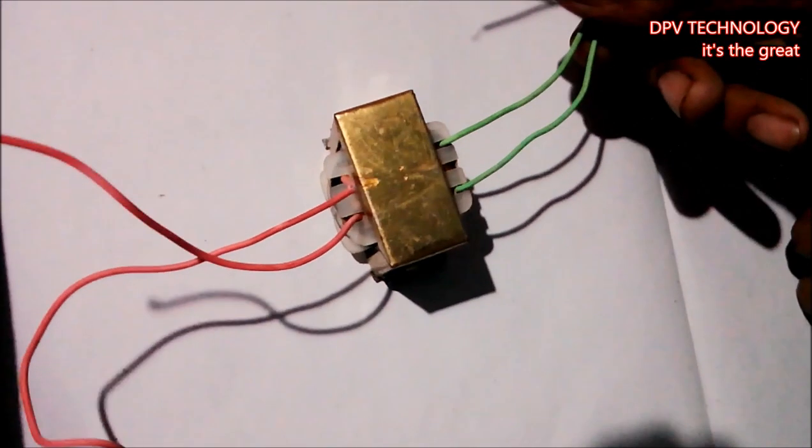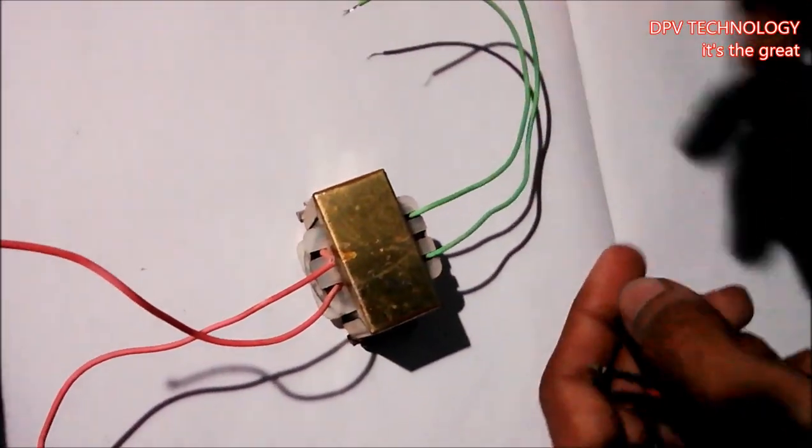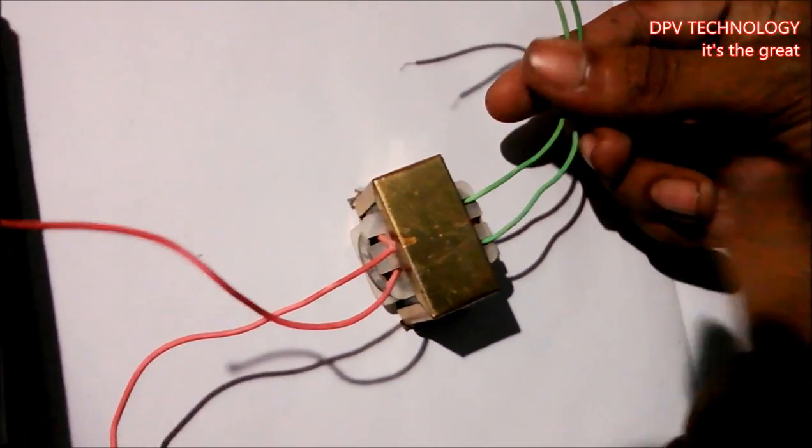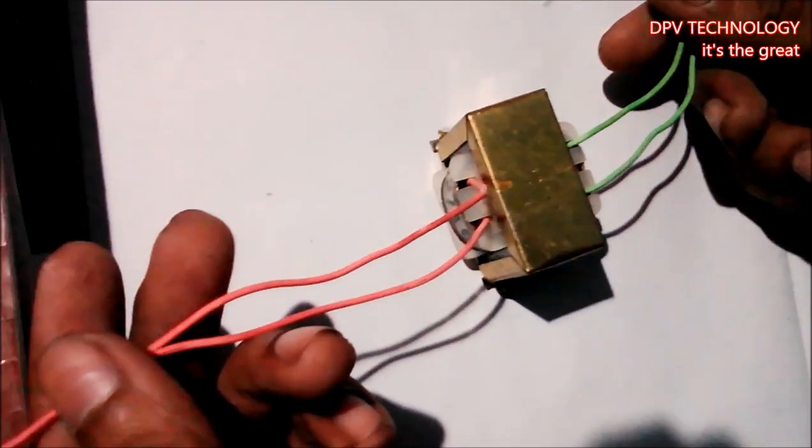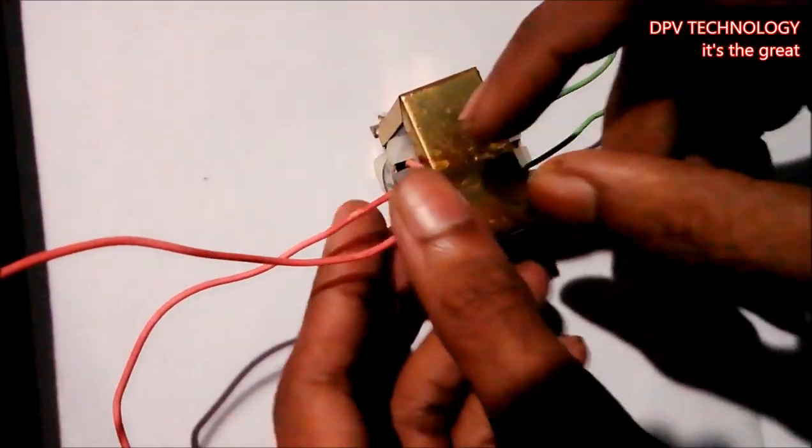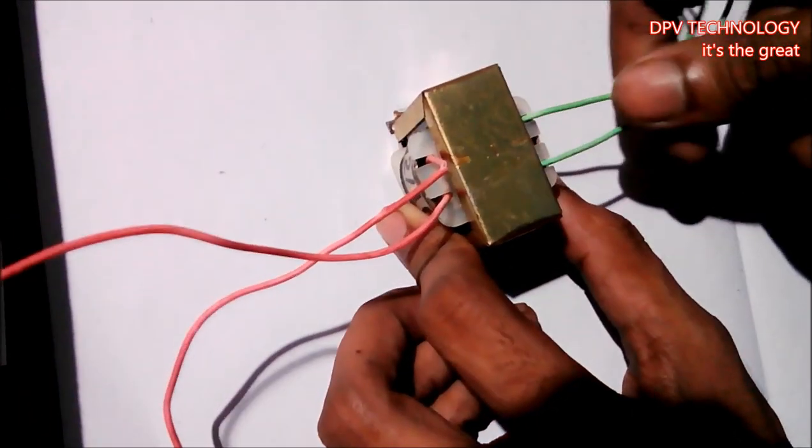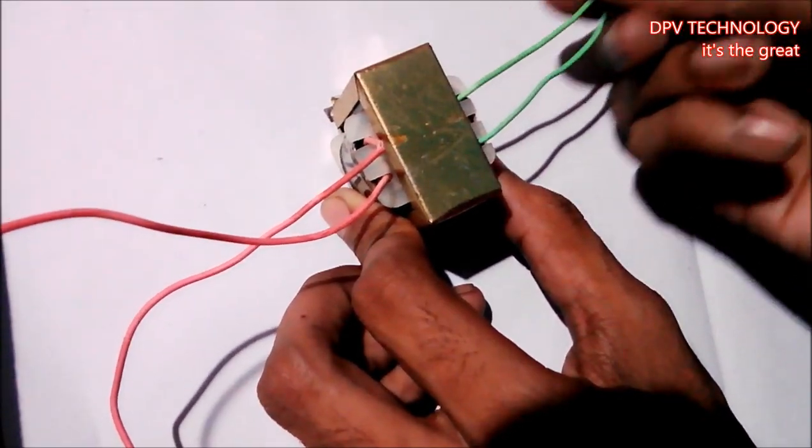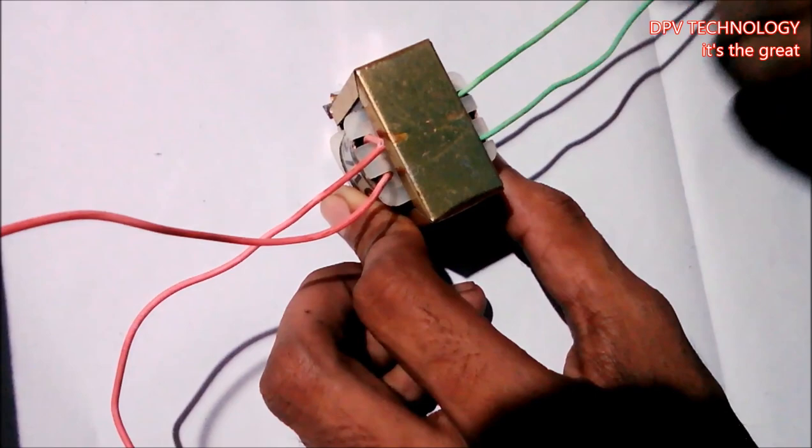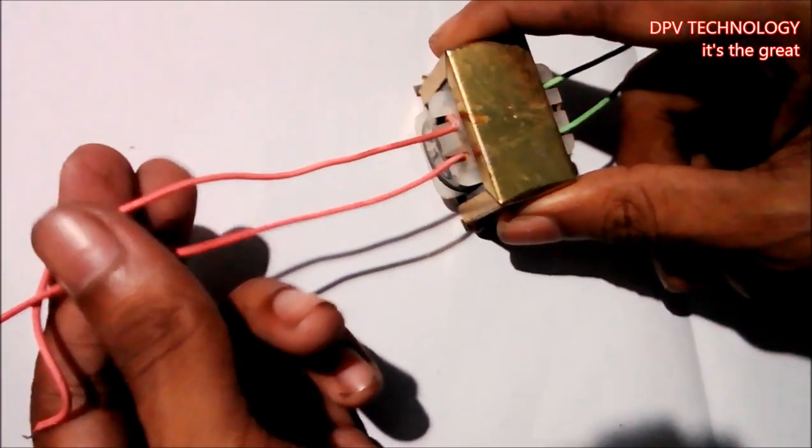Here we have 1.6 kilo-ohms. So this is the secondary side. The resistance of the secondary side is always lower than the resistance of the primary side. This is because the primary side has more turns than the secondary side. Lower resistance means secondary side, and higher resistance means primary side.